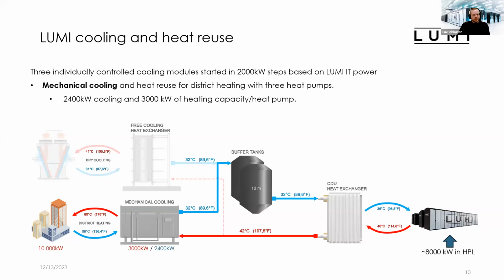Then about the cooling itself, these are the same slides that I had yesterday, but I will go through these quickly. So this mechanical cooling, we are actually utilizing all the waste heat from the Lumi. Depending on the Lumi IT load, we are able to operate up to the 9 megawatt of district heating with these 3 heat pumps. So all the cooling is done with the heat pumps. Mechanical cooling is utilizing this 32 Celsius outlet through the buffer tanks back to the Lumi. And return temp is somewhere 42 to 44 degrees. It depends a little bit how much load there is in the Lumi.